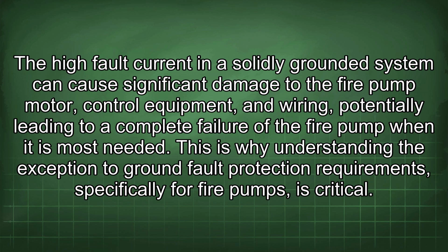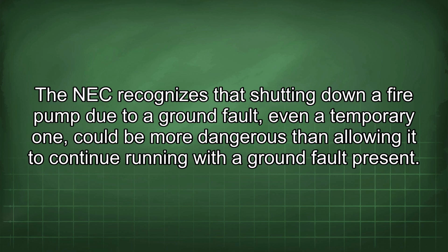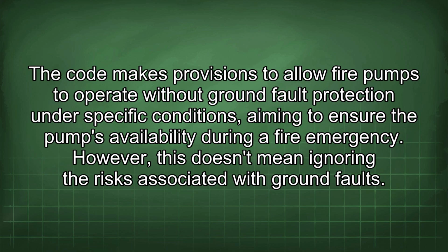This is why understanding the exception to ground fault protection requirements specifically for fire pumps is critical. The NEC recognizes that shutting down a fire pump due to a ground fault, even a temporary one, could be more dangerous than allowing it to continue running with a ground fault present. The code makes provisions to allow fire pumps to operate without ground fault protection under specific conditions, aiming to ensure the pump's availability during a fire emergency.